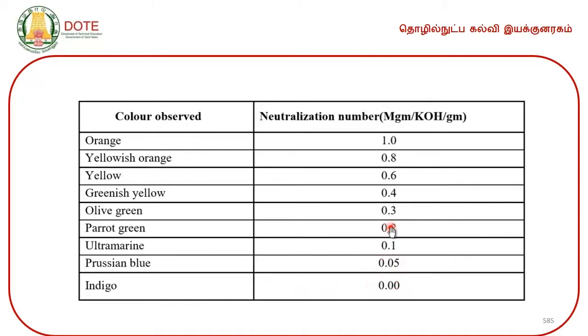So, up to 0.2, that is, when the color is indigo or Prussian blue, then ultramarine, up to parrot green, the condition of the transformer oil is considered to be good. You cannot afford to change it at this point. From 0.2 to 0.5, then you have to consider. From 0.5 to 1 onwards, the other conditions apply.